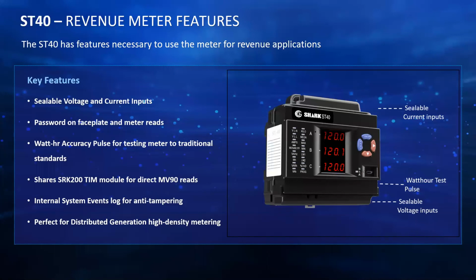This is also perfect for distributed energy high density metering. So if you have a solar panel, a solar farm, and there's no switchboard to put a meter in, again, this is just a DIN rail mount. Again, with solar farms, we see a lot of harmonics that are being generated, using the power quality functions. You can measure the energy being generated, since this is a bidirectional meter. So not just the energy consumed, but it can also monitor the energy being generated by the solar farm, and also give you that additional power quality information with waveforms and harmonics.